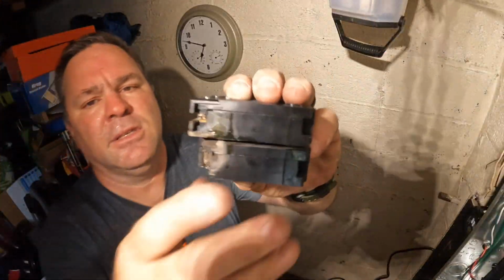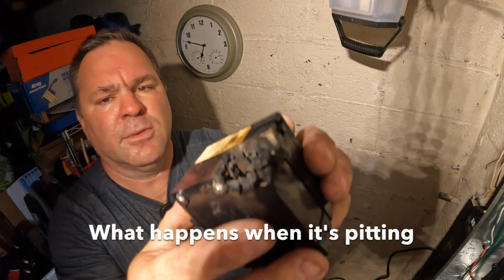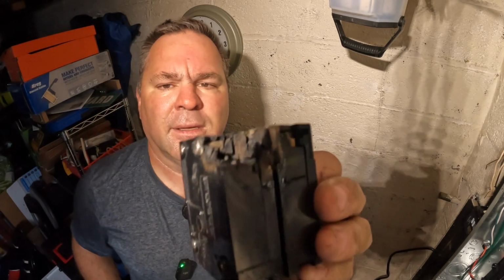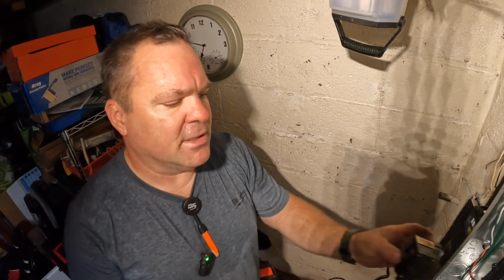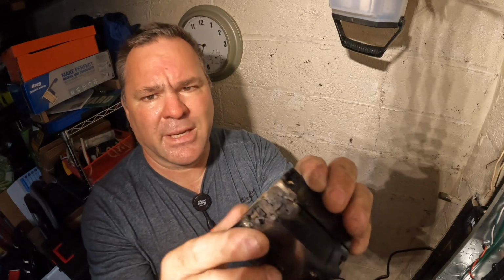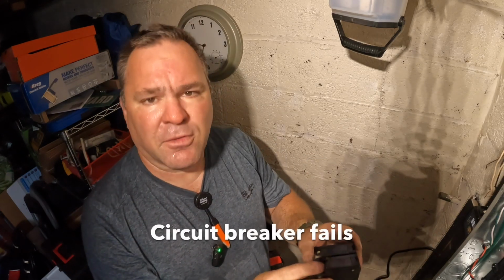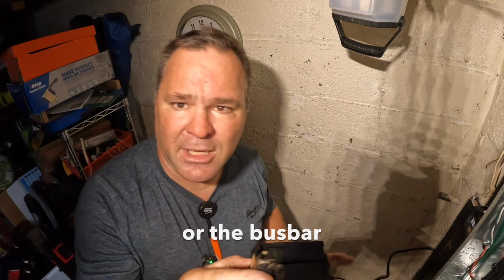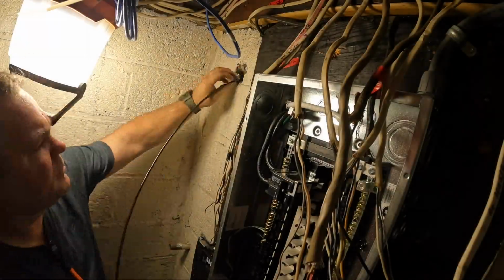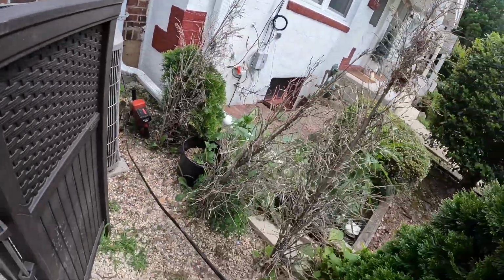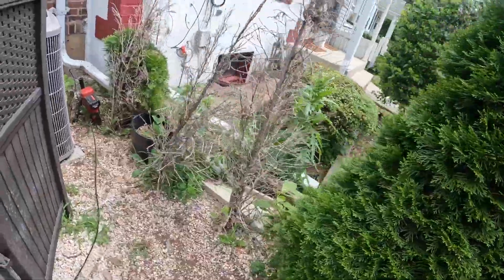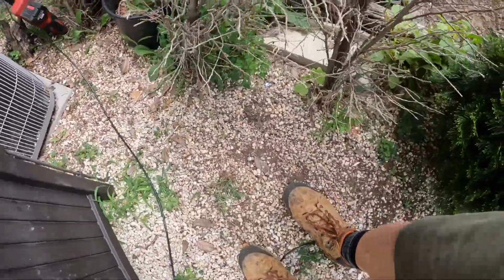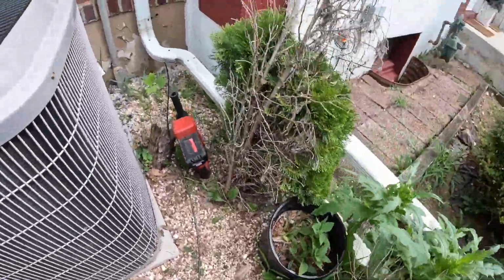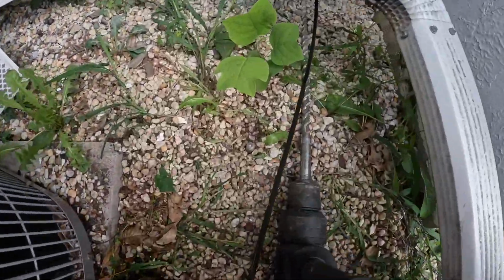Alright, so as you can see here, that's what happens when it's pitting. We'll call that pitting up against the bus bar. It's just not making the right connection. So either the circuit breaker failed or the bus bar, or a combination of the two, and I believe it was a combination of the two. I think what we'll do is we'll attach this first. And then I drove the other one here using my SDS Max.